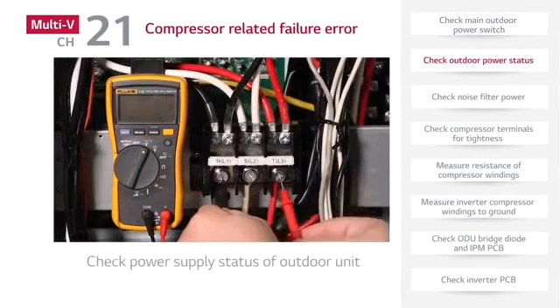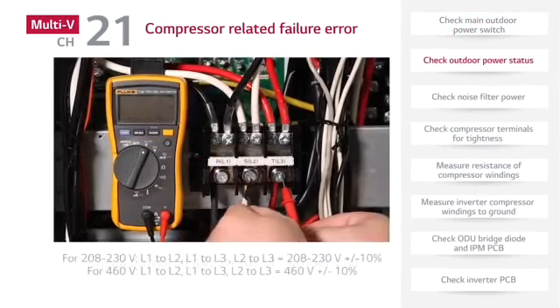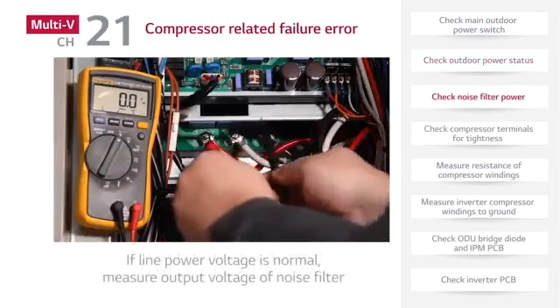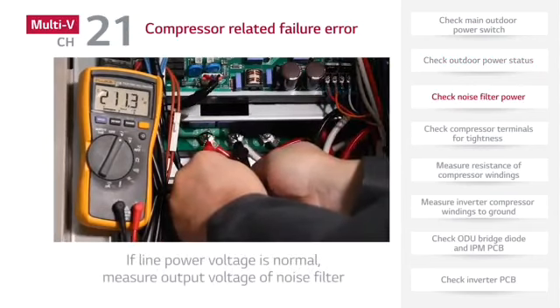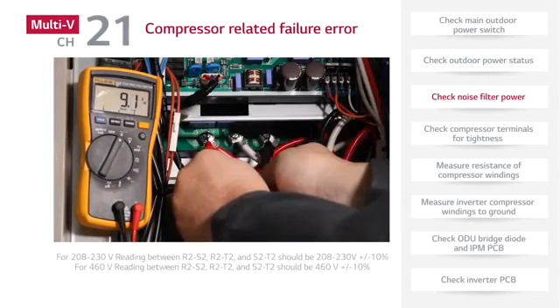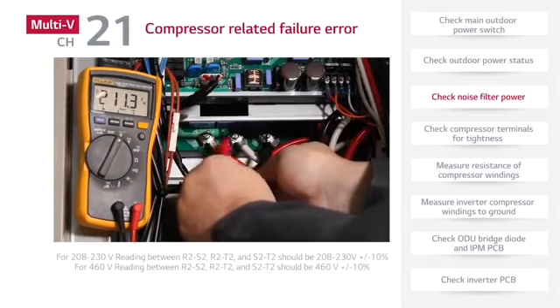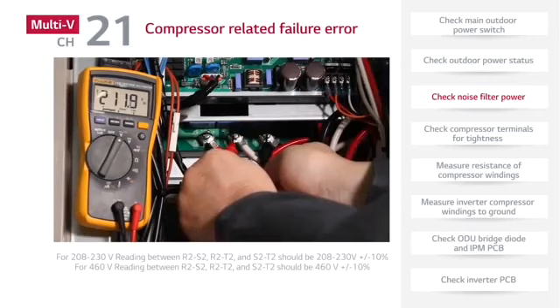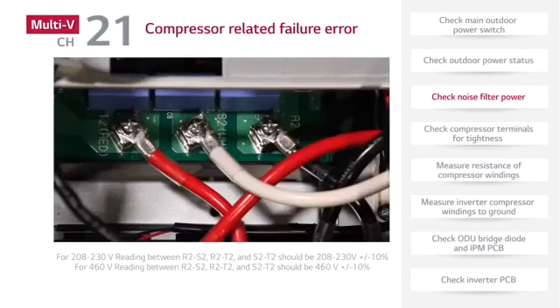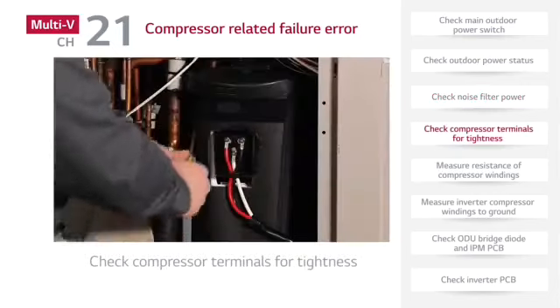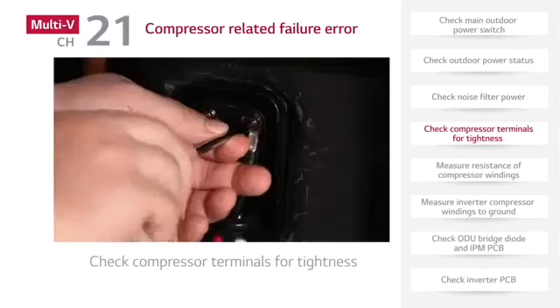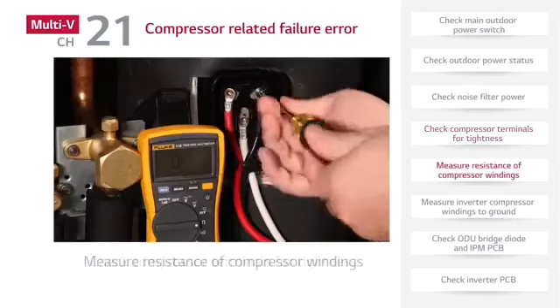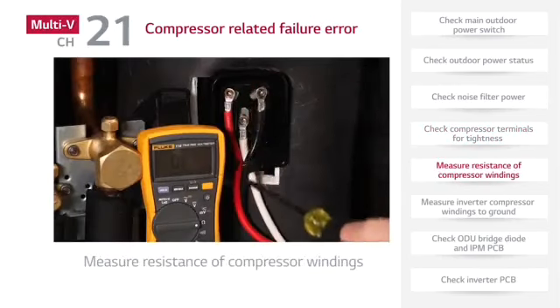Next, check outdoor unit power supply status. Check the noise filter output voltage. If there is no problem with the noise filter, disconnect power and check the compressor terminals for proper tightness. Next, measure the resistance of the compressor windings.